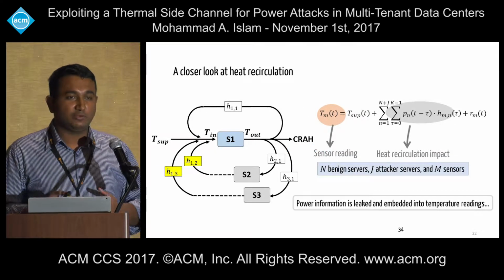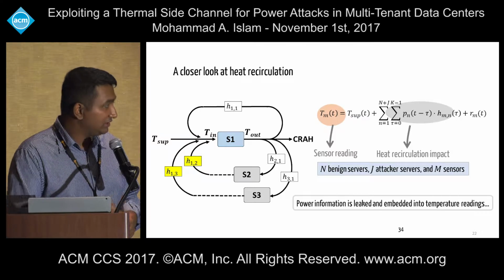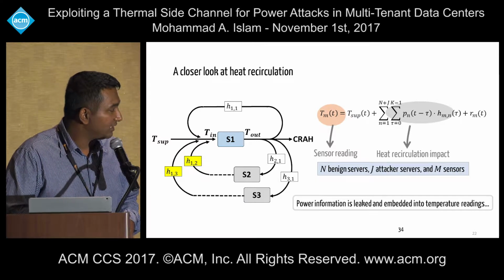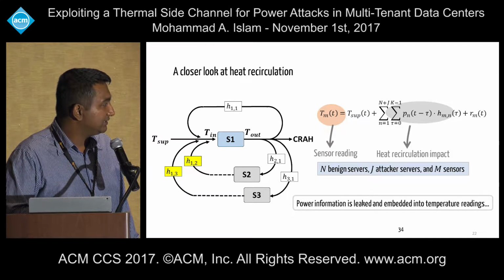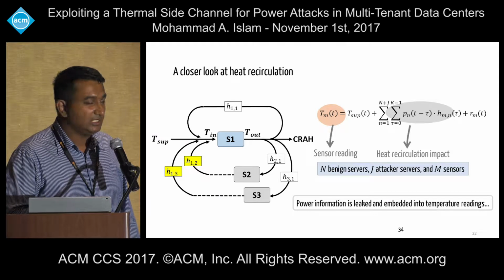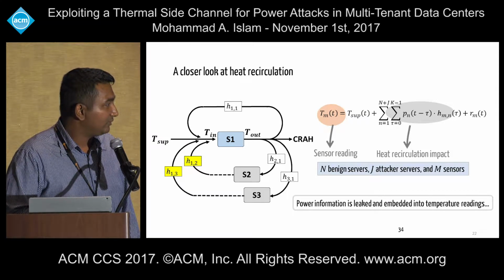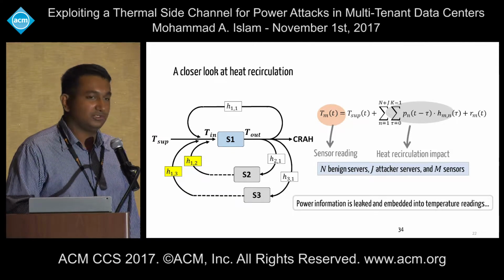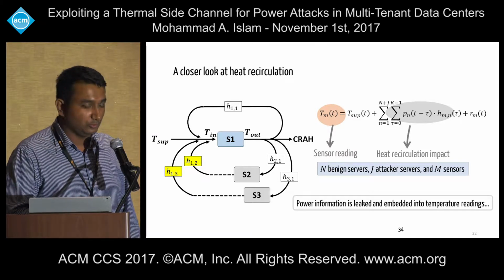Let's take a closer look at heat recirculation. Consider three servers, S1, S2, and S3. T-supply is the supply temperature coming from the AC. T-in is the inlet air temperature of server 1, and T-out is the exhaust air temperature of server 1, which is sent back to the computer room air handler to be cooled again.